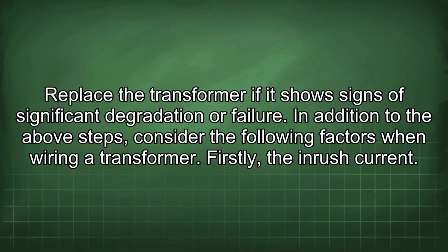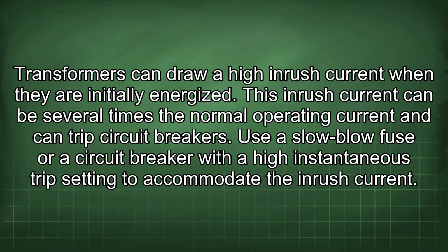In addition to the above steps, consider the following factors when wiring a transformer. Firstly, the inrush current. Transformers can draw a high inrush current when they are initially energized. This inrush current can be several times the normal operating current and can trip circuit breakers. Use a slow-blow fuse or a circuit breaker with a high instantaneous trip setting to accommodate the inrush current.